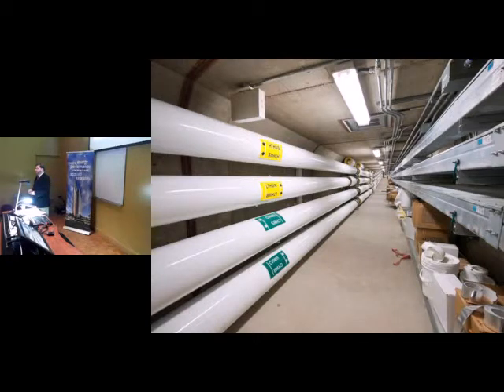That hot water is so hot you can't touch it, though it's not boiling. It comes across through the tunnel into the terminal building, and we first send that very warm water through all the heating elements on the perimeter—anywhere there's an entry door, a rolling door for vehicles, or a window with a radiator at its base. We run the hottest water to those elements first, since they see the greatest temperature differential and cool off relatively quickly as the water passes through.